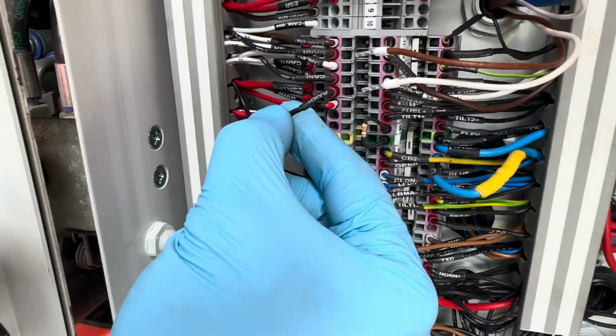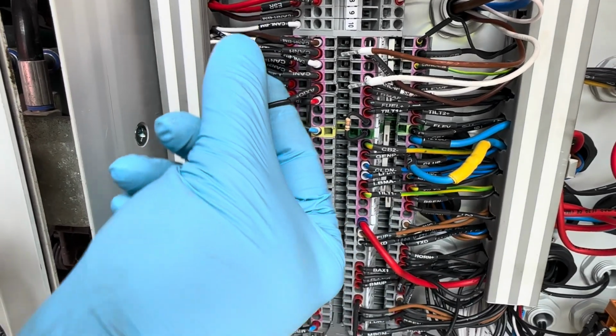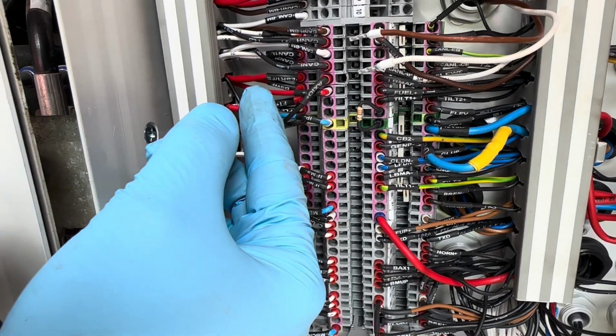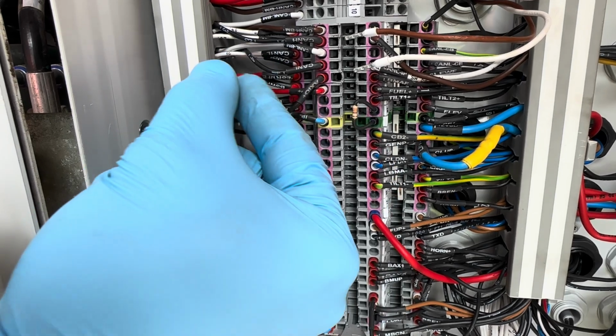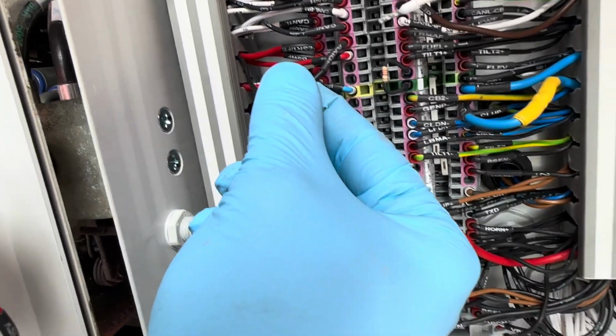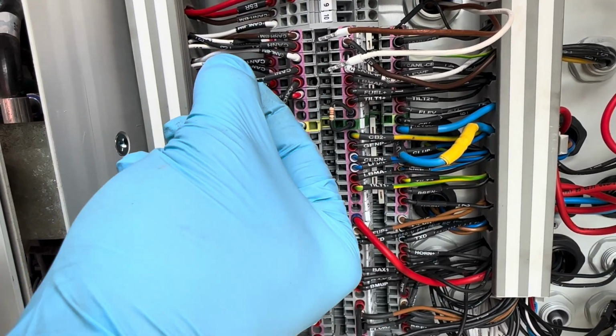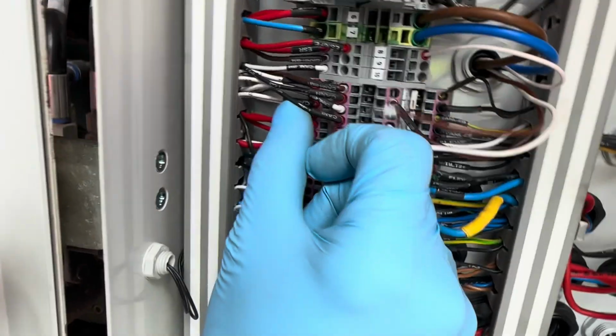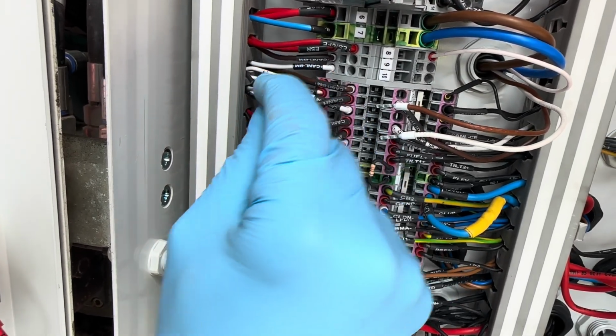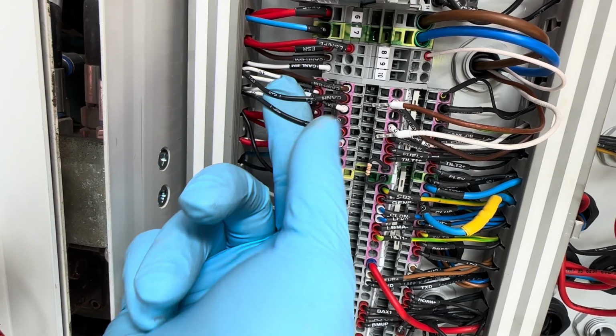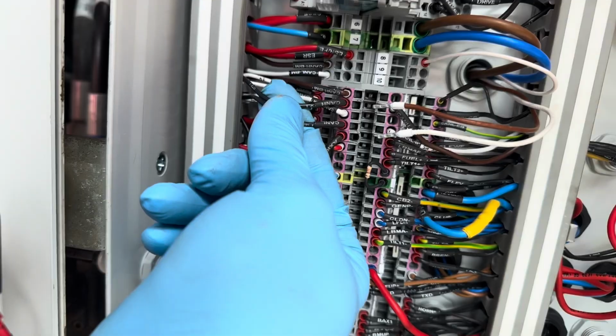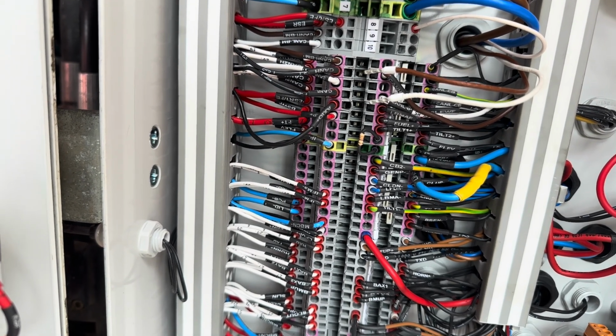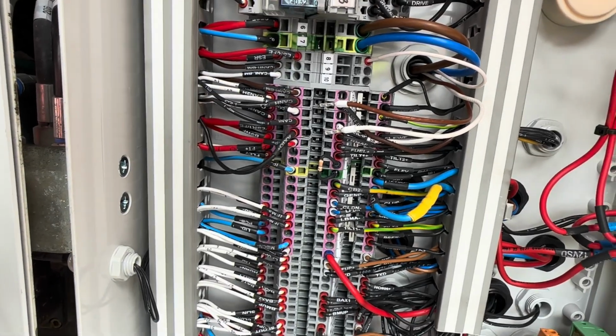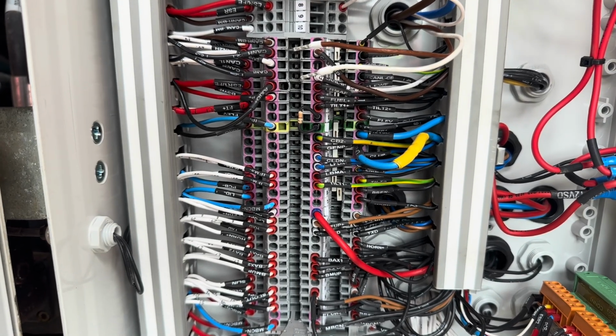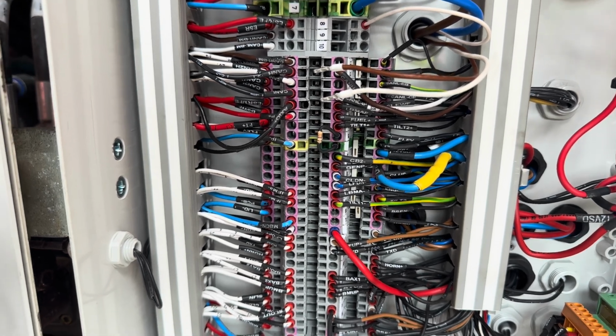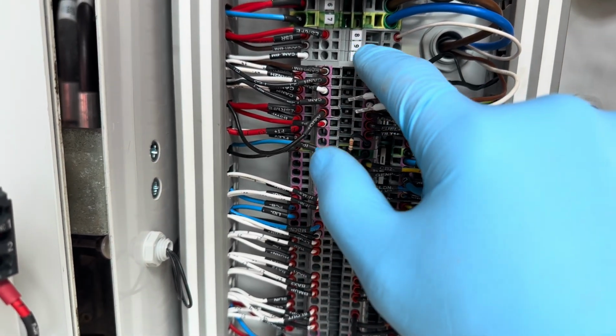So these wires here, Axio plus, that's your power supply to the valve driver. And then you have CAN low, CAN high, cord number 4 and 3. That's the wires that connect the axiomatic valve driver into the Canbus. So I will remove them, and we're gonna go by process of isolation, and then we're gonna retest the resistance on terminal 9 and 10.